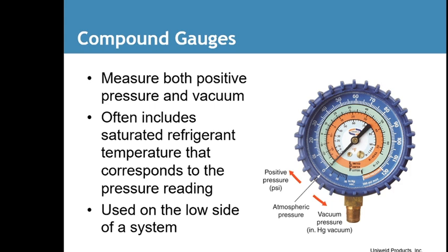If it goes down from 0 or counterclockwise, it shows vacuum pressure, which is measured on a gauge in inches of mercury. Hg is the chemical symbol for mercury. So it's just showing you how much it's pulling down. And again, to pull a good vacuum on a home system, to get it to 29.93 inches of mercury is great. But sometimes you can't do that.